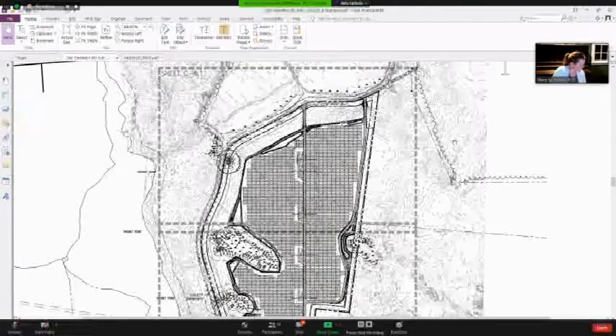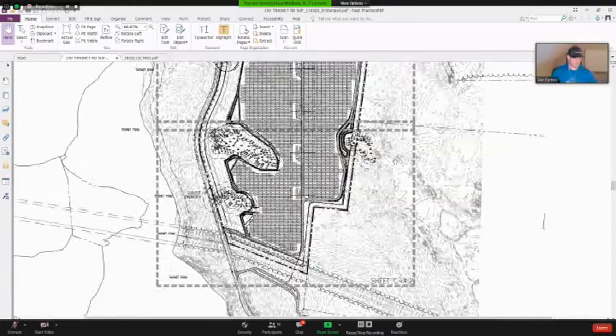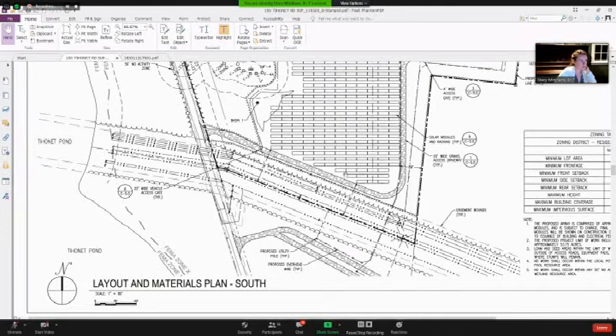Number 5 just asked that Borrego explain why the overhead wire connections from the existing power line easement to the project site. So this is something where for this particular site, actually, let me get to a plan that shows the connections. So for this site, Borrego would like to stay overhead. This is obviously the southern portion of the solar, the existing high voltage lines, and then the interconnection information here, which is proposed as utility poles overhead. I think given the context, adjacent, setback from Thonet Road, but adjacent to the existing high voltage lines, it's appropriate for overhead here. I guess that's the preference, but wanted to discuss with the board.